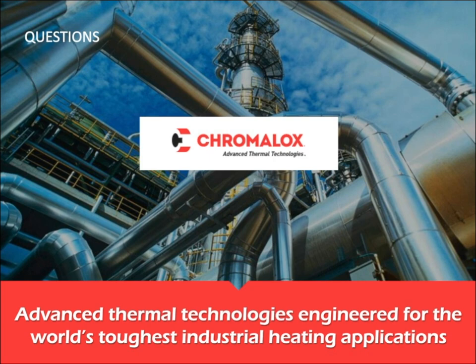So a medium voltage system can be provided with an IEC, an ATEX, Class 1, Zone 1, similar applications, and it can be located directly in your hazardous area. So back to the previous question, when you talk about efficiency, that's why the efficiency can be so high, because you don't have to worry about transmitting over long distances. That heat can be supplied directly at the source. So yes, it can be located in your hazardous area with no issues.